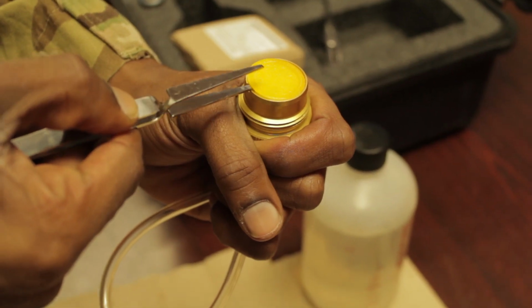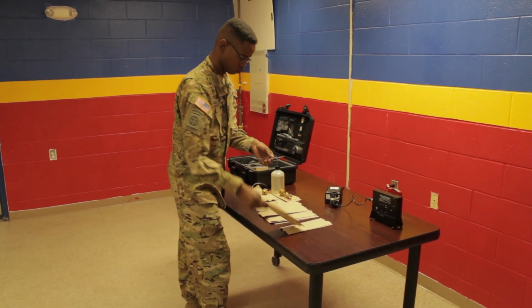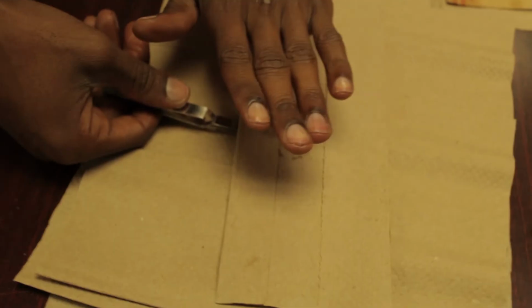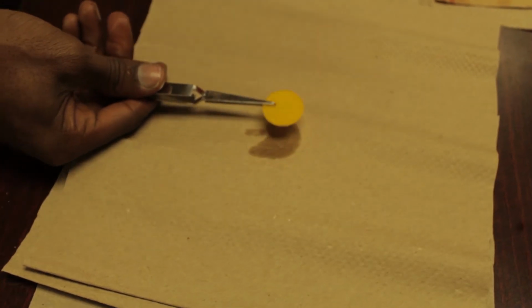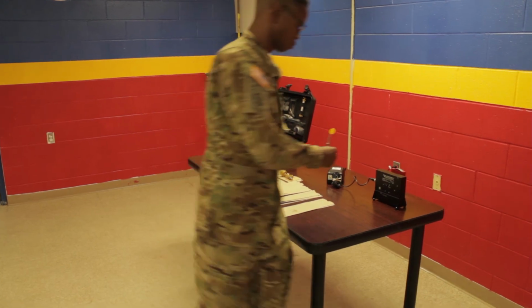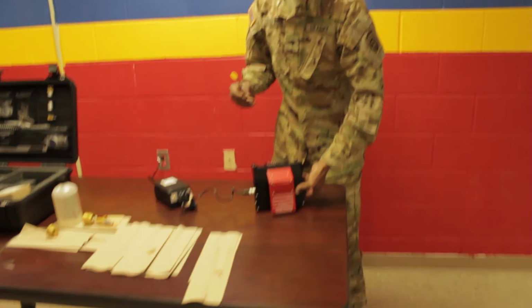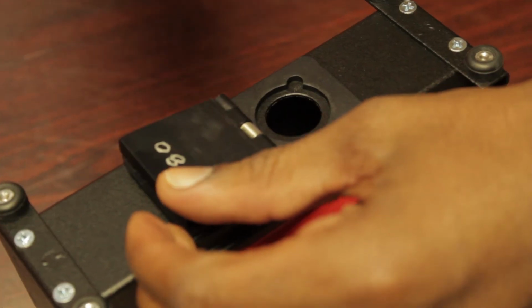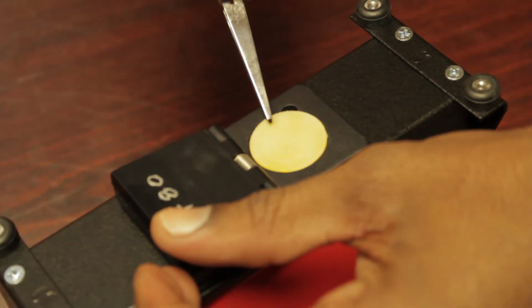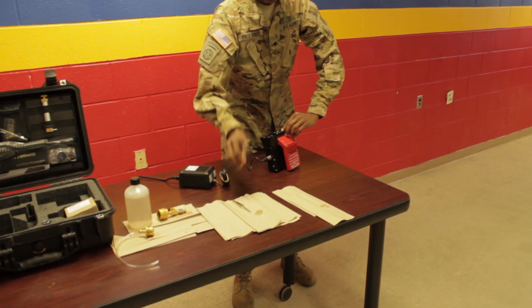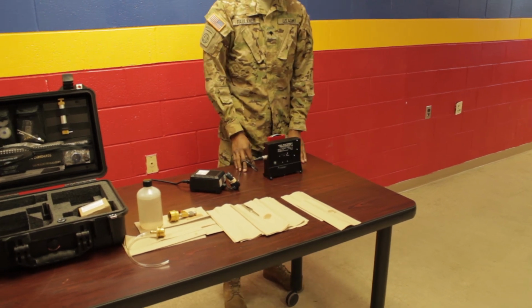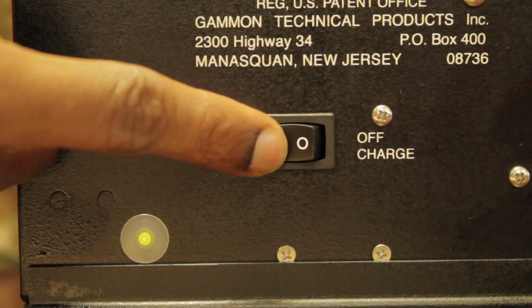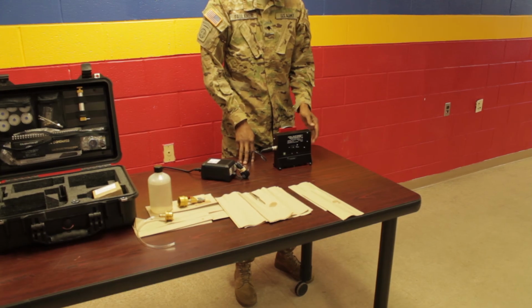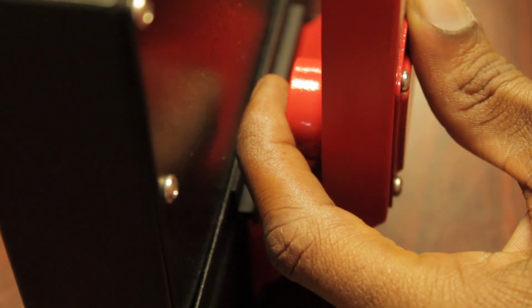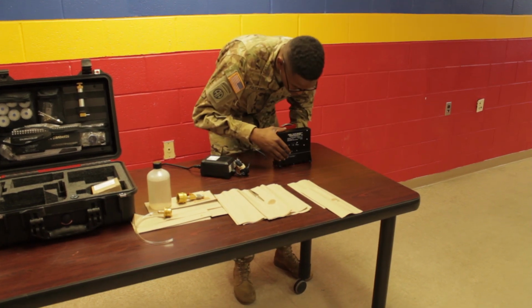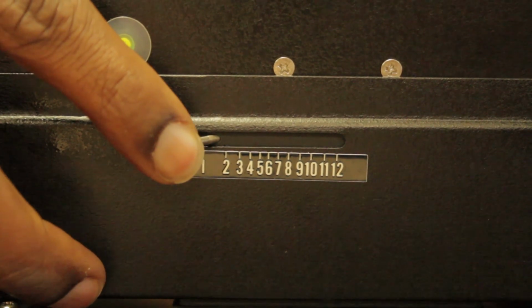Remove the test pad from the holder using tweezers and blot the test pad between clean, dry paper towels to remove excess fuel. Using tweezers, place the Aqua Glo test pad in the bottom portion of the ultraviolet lamp assembly. Ensure that the orange side faces the ultraviolet lamp. Turn on the power to the Aqua Glo test kit. Press the hooded button of the meter assembly while moving the light modulator lever. Watch the meter scale while moving the light modulator lever until the meter pointer lies on 0.